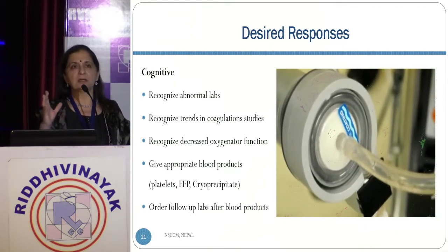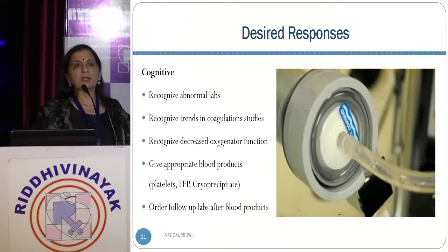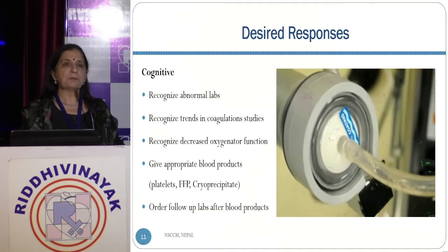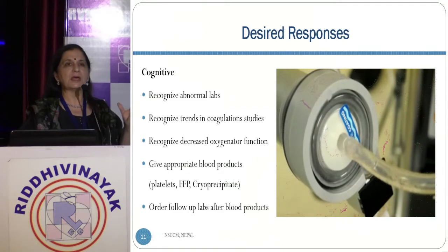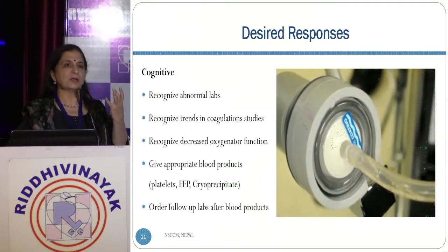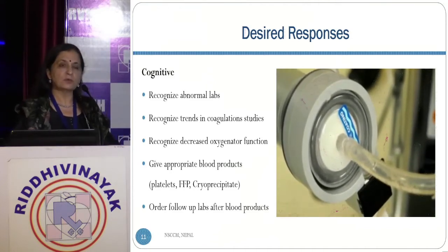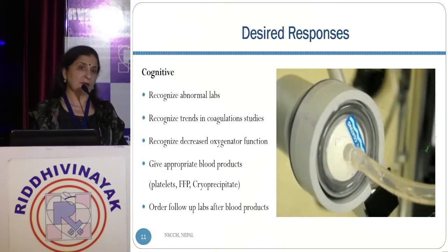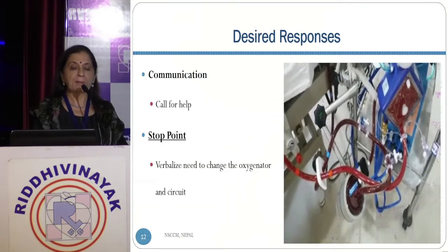Also, keep monitoring the revolutions per minute of the centrifugal pump. They're important. The Medtronic pumps that we use at AIIMS, we use very little of the Maquet pumps, but we use the Medtronic pumps and the Sarns pump. These are bigger pumps, as was told to you in the morning, with higher flow rates. And the moment your flow rates are high, your hemolysis is more. So look out for thrombosis as well as more hemolysis, and also look out on day 7 and above, particularly in children, for intracranial hemorrhages.